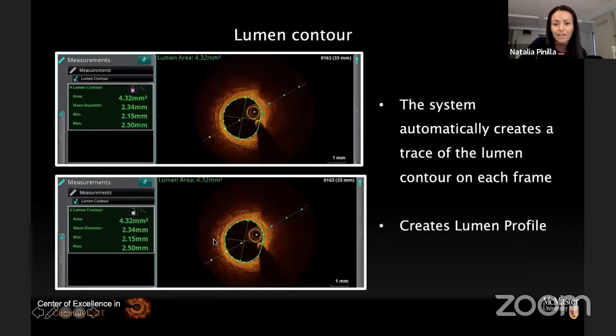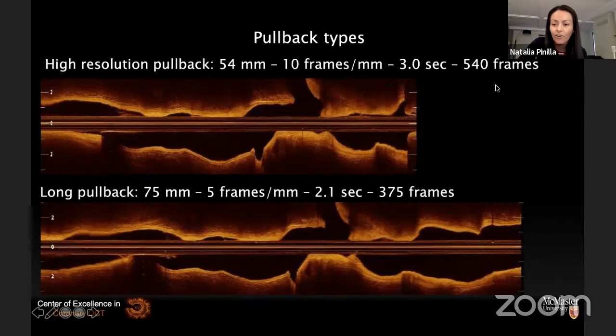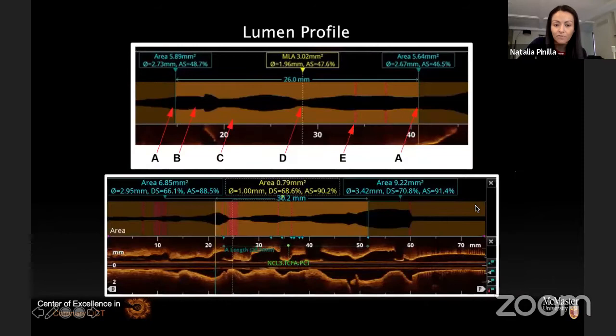What is important and amazing about OCT is that it performs automatic area detection in every single frame — 540 frames in the 54mm pullback or 375 frames in the 75mm pullback — and puts all those areas together into a reconstruction called the lumen profile. This has changed the way we plan PCI, because never before did we have a tool that assembled all the areas and gave us a real assessment of the whole vessel architecture.